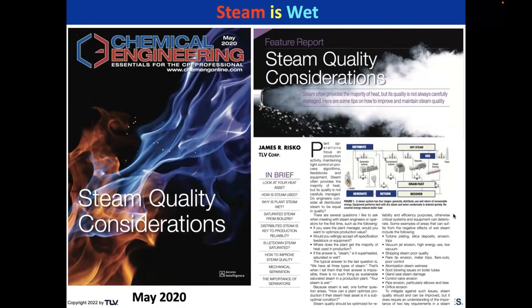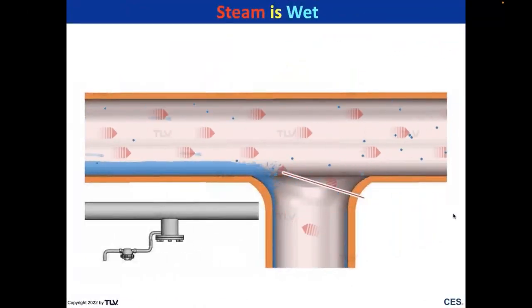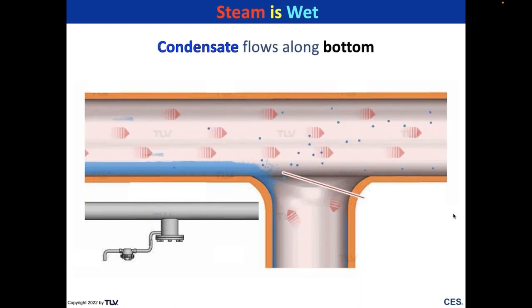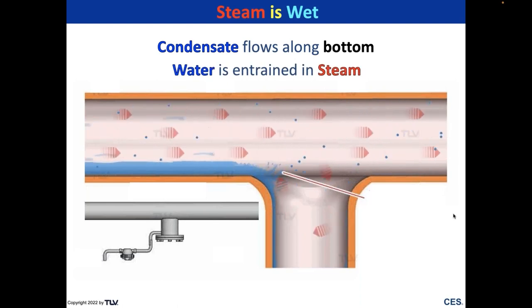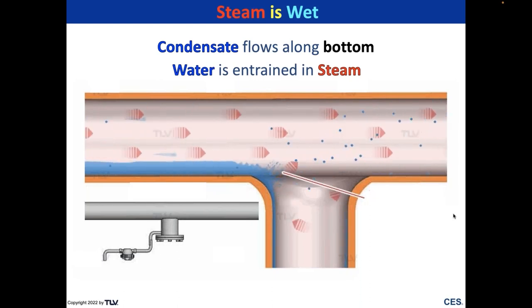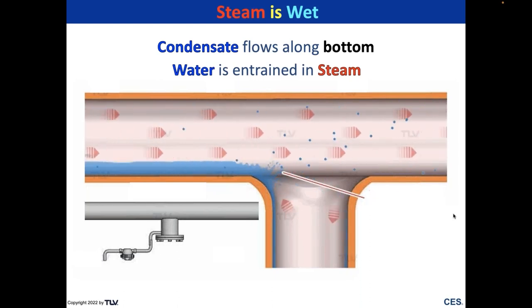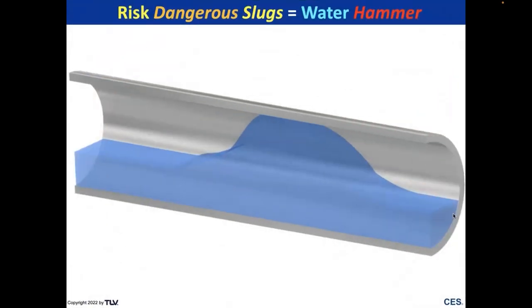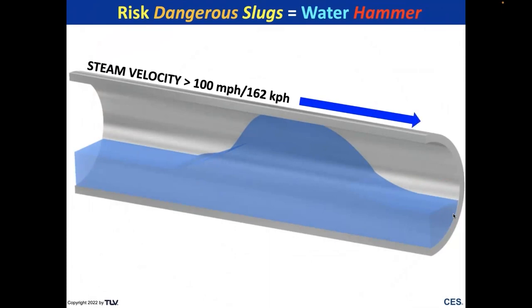If you want to read more about that, I wrote an article in Chemical Engineering two years ago titled 'Steam Quality Considerations,' available on the TLV.com website and Chemical Engineering's website. More accurately describing what steam looks like: you've got condensate flowing along the bottom of the pipe and water entrained in the steam. With superheated steam you probably won't have water entrained in the steam, but you can still have water flowing along the bottom.